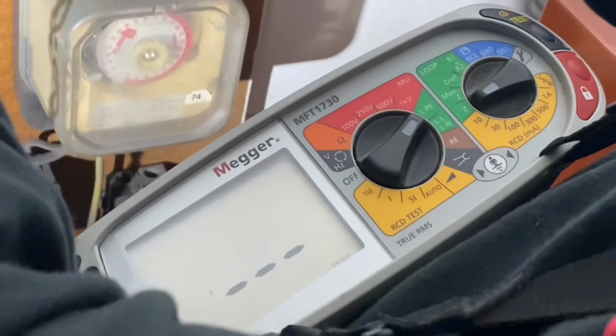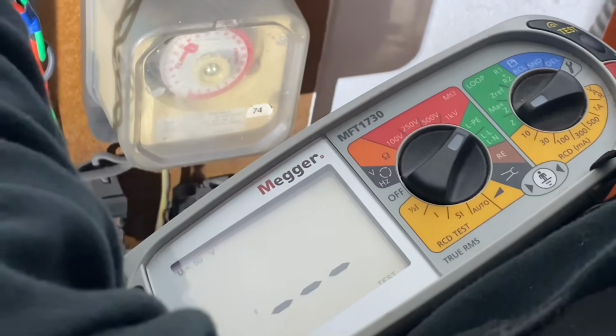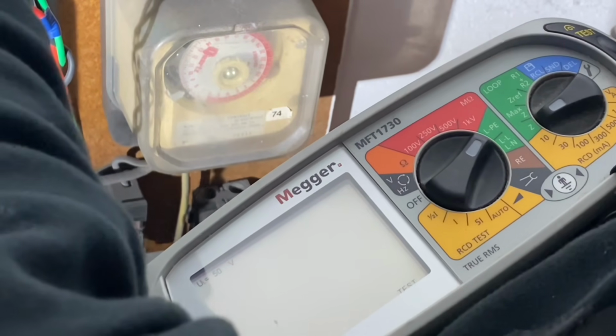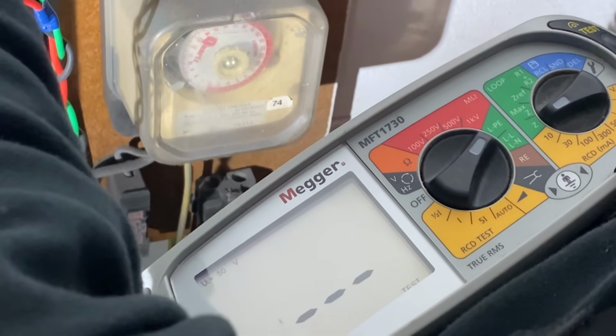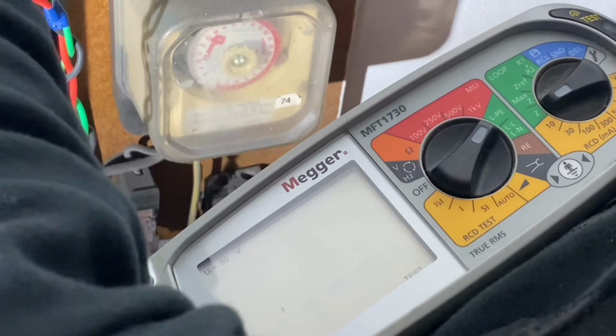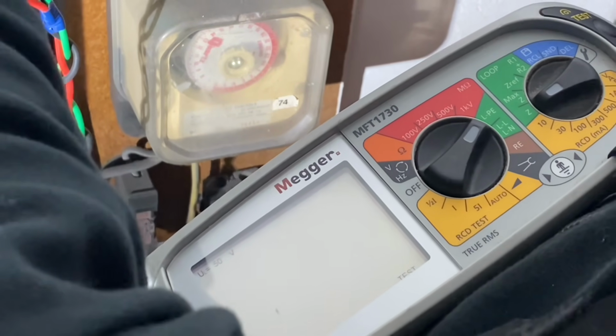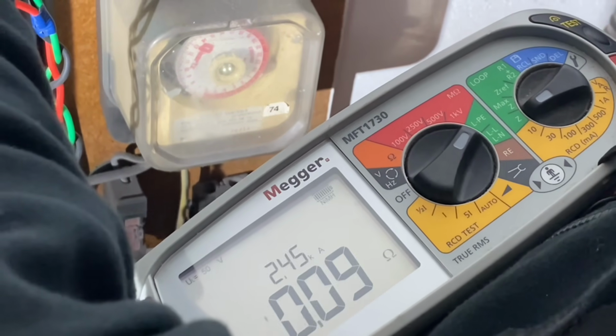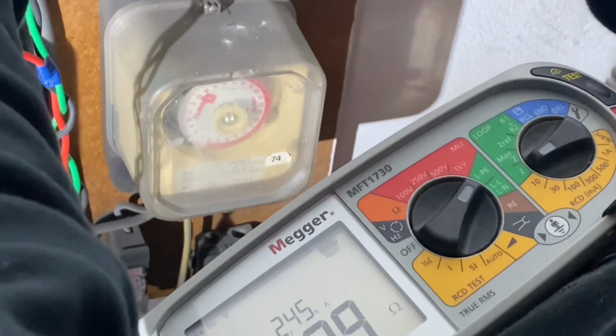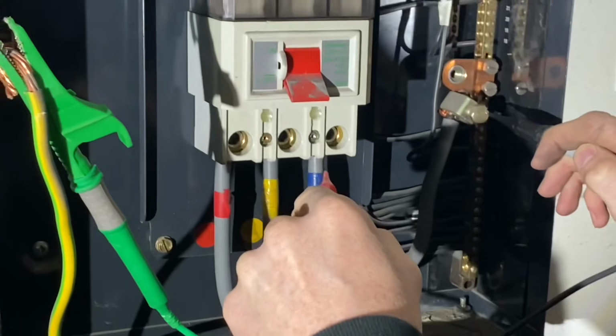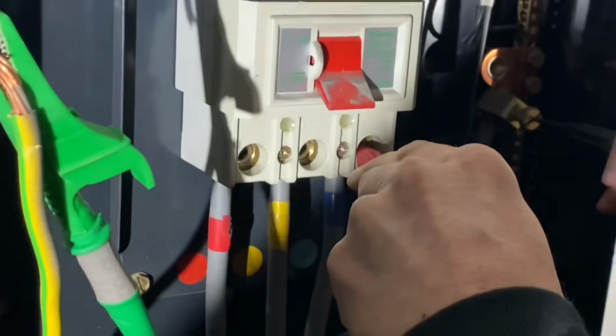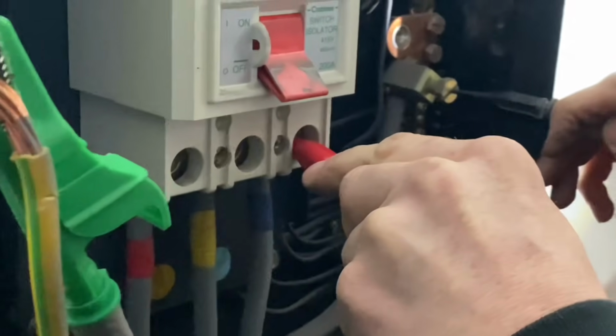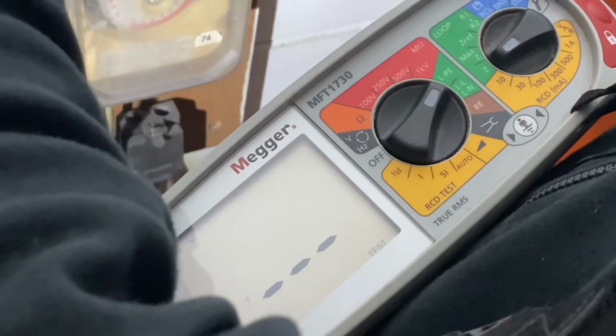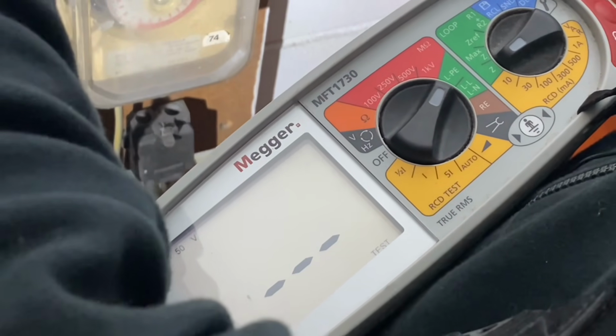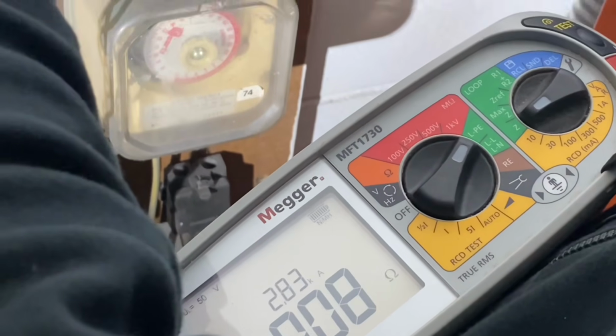Again, because we're going between neutral and phase, it's detecting a single-phase voltage. I think it's about 240 volts in here. Of the three readings we take, which one are we going to record? It's just the highest reading. Okay, so we've got to remember we've got 0.08, now we've got 0.09, so that's now the highest one. And then we'll probe back off. If you notice, every time I physically take the probes back off in the right order, exactly the same as we do for supply polarity and safe isolation. Right, 0.08 of an ohm.